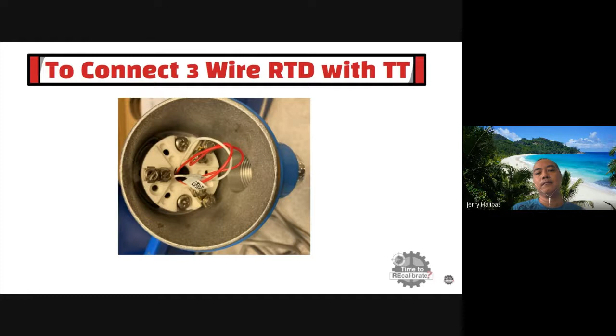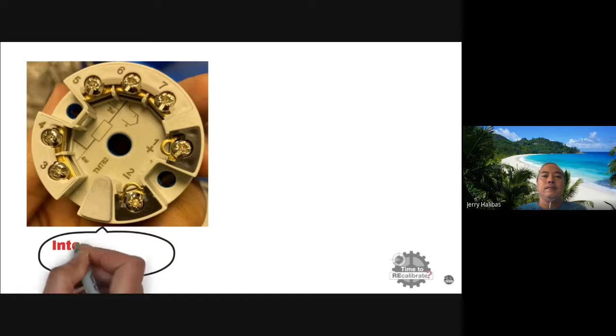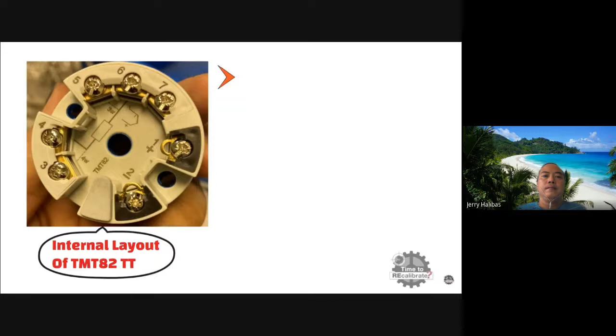Now, let's learn how to connect a 3-wire RTD to a temperature transmitter. As you can see, this is a typical 3-wire RTD, and I am going to connect this RTD to a temperature transmitter. In this example, I will take the E&H TMT82 temperature transmitter. As you can see, this is the internal terminal layout of the temperature transmitter. In this temperature transmitter, terminals number 4, 5, and 6 are for sensor input. In other words, the RTD's wires are connected to these terminals. It will be shown in the next slide step by step. In addition to this, terminals number 1 and 2 are for power supply.